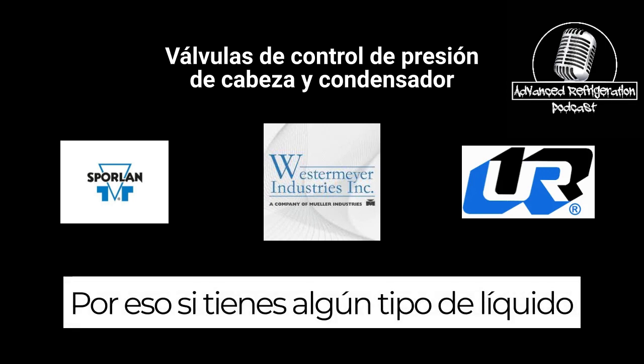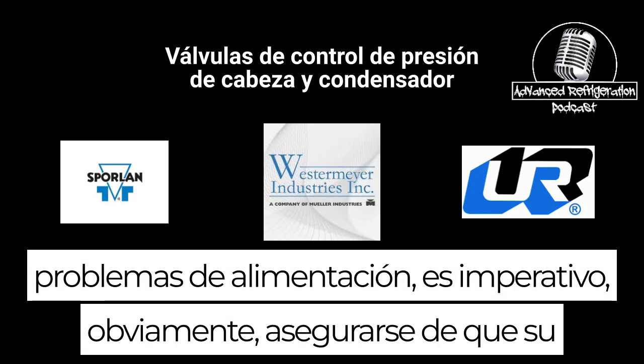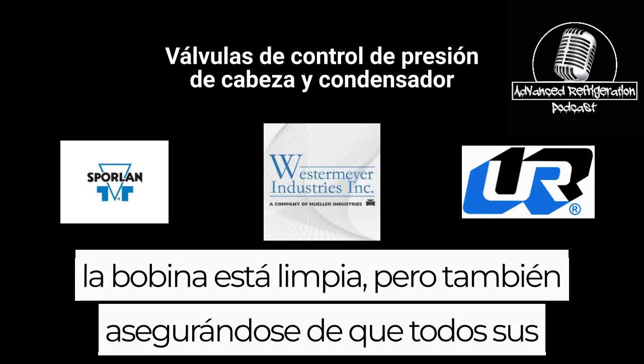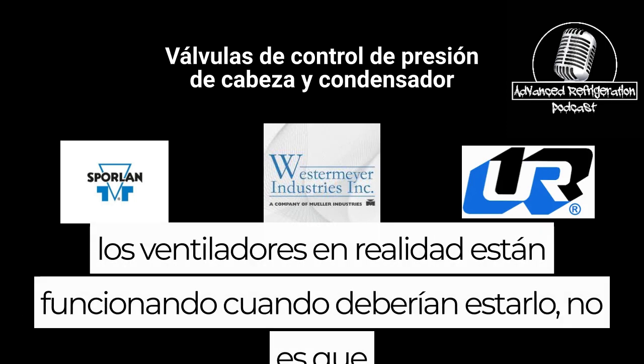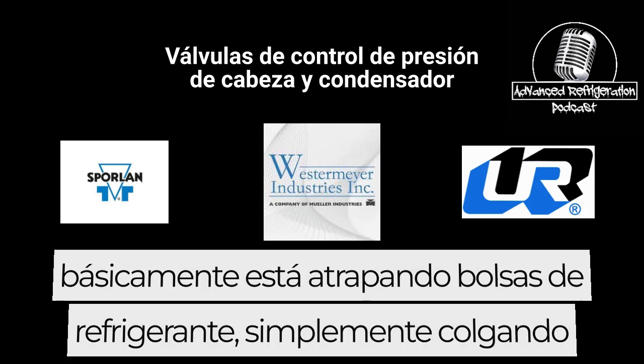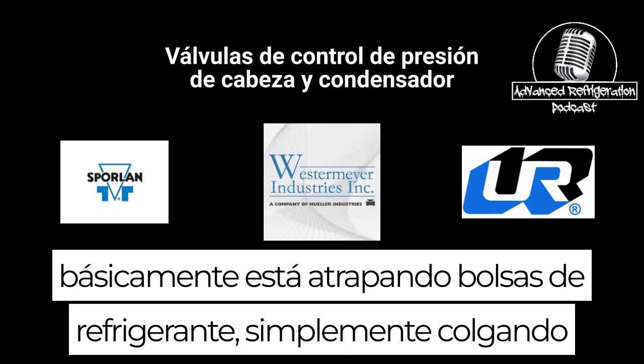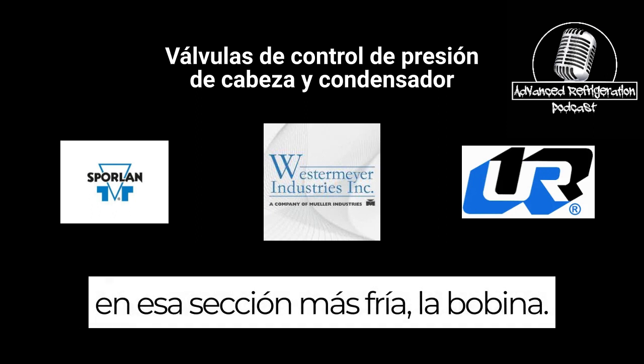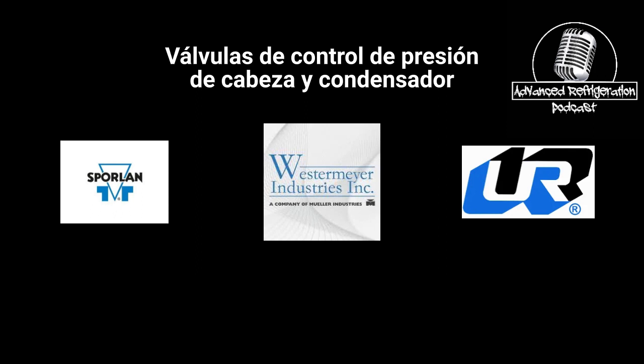That's why if you do have any kind of liquid feed issues, it's imperative, A, to make sure that your coil is clear, but also to make sure that all your fans are actually running when they should be. Otherwise it's basically catching pockets of refrigerant that just hang out in that one colder section of the coil.